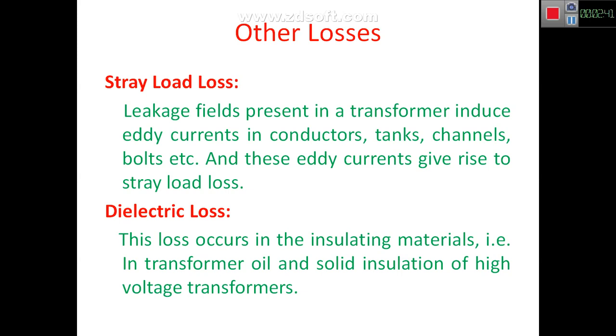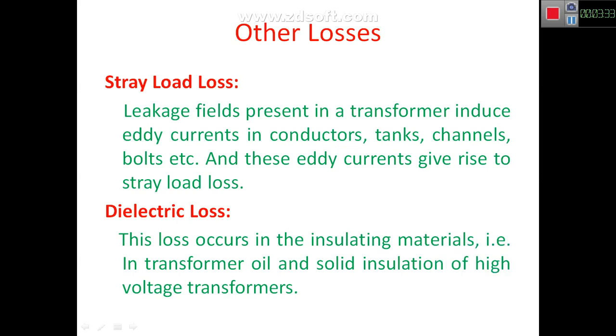The other losses are stray load loss and dielectric loss. Stray load loss is essentially eddy current loss caused by leakage flux — the leakage field induces eddy currents in conductors, tanks, channels, bolts, and other structural materials of the transformer. Dielectric loss occurs in insulating materials such as transformer oil and solid insulation used in high-voltage transformers.